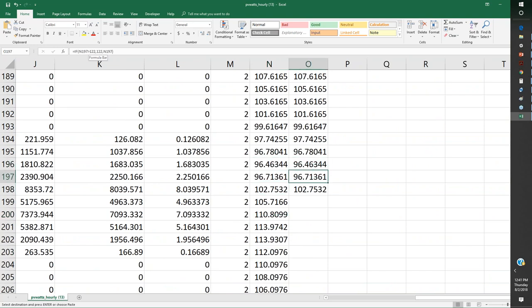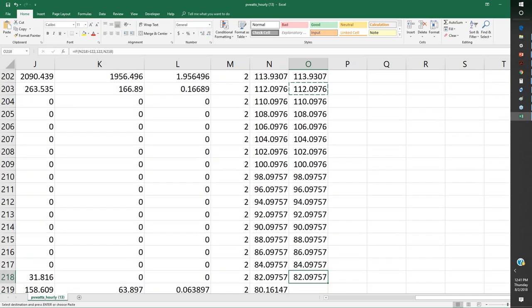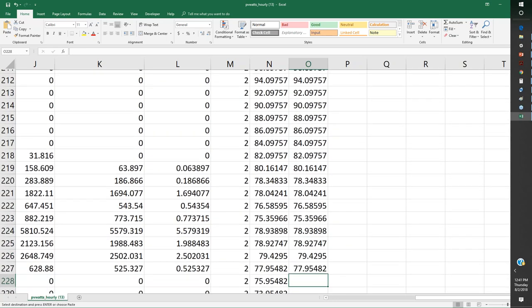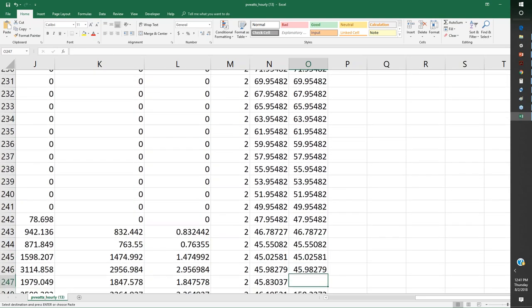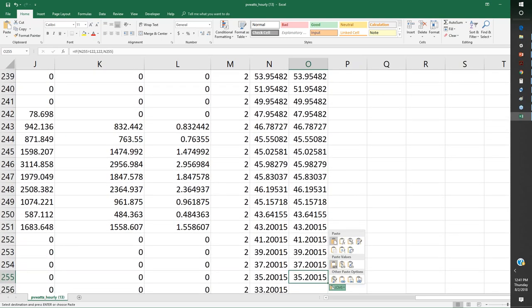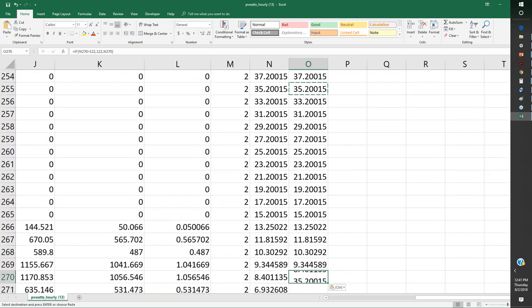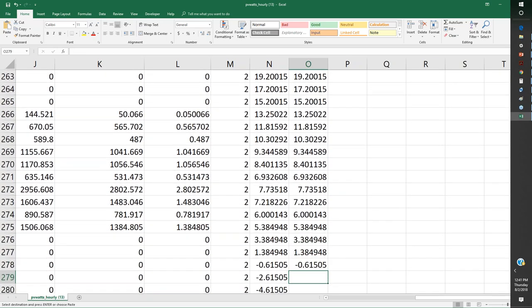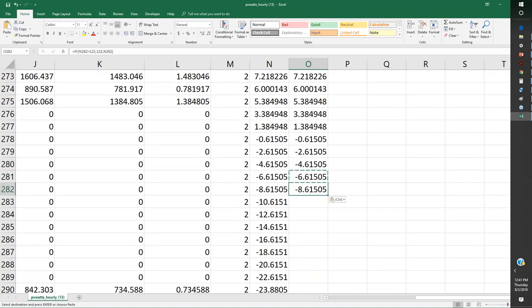And so what we're doing in this exercise is modeling the battery capacity for every single hour of the year, based off the actual performance of the solar array and also based on the actual size of our battery bank. And so what we can see is now we're getting into the cloudy weather system, and what was a 120 kilowatt hour battery bank only has 3 kilowatt hours left, only has 2 kilowatt hours left. Now we're at a negative six deficit.